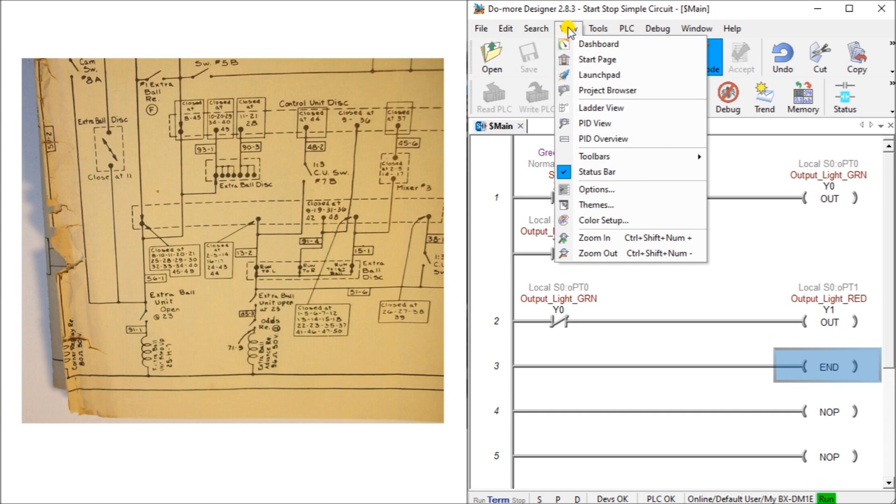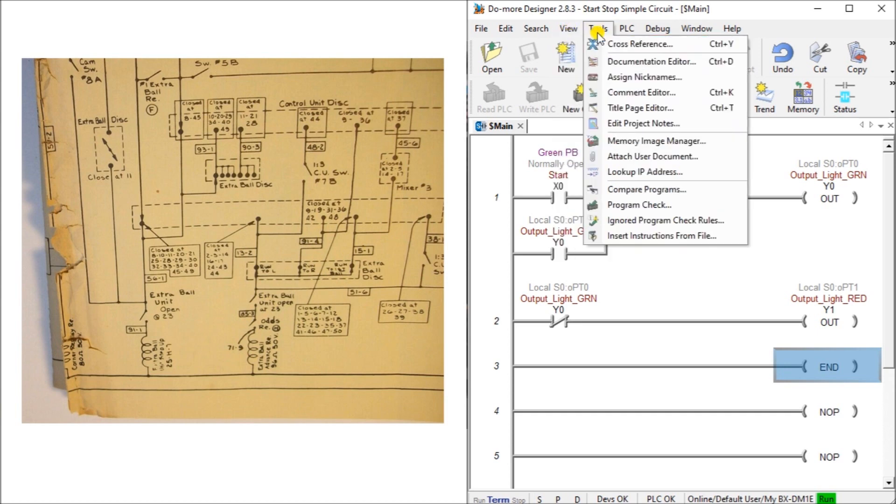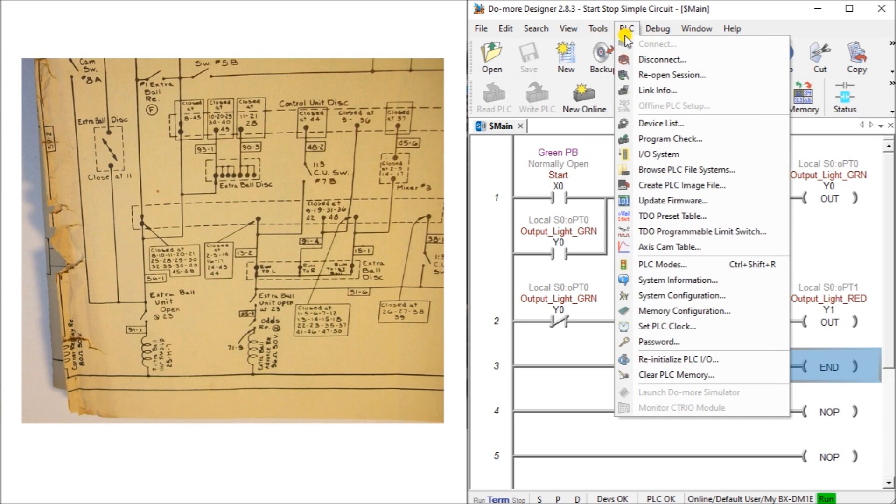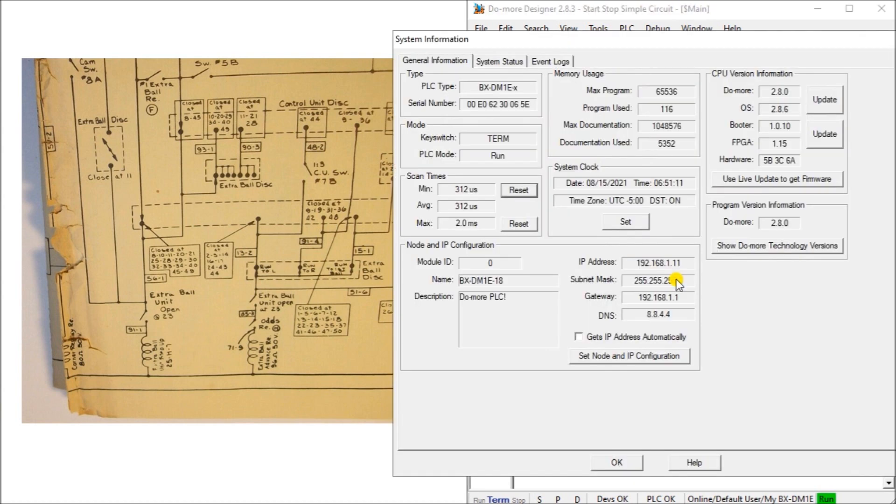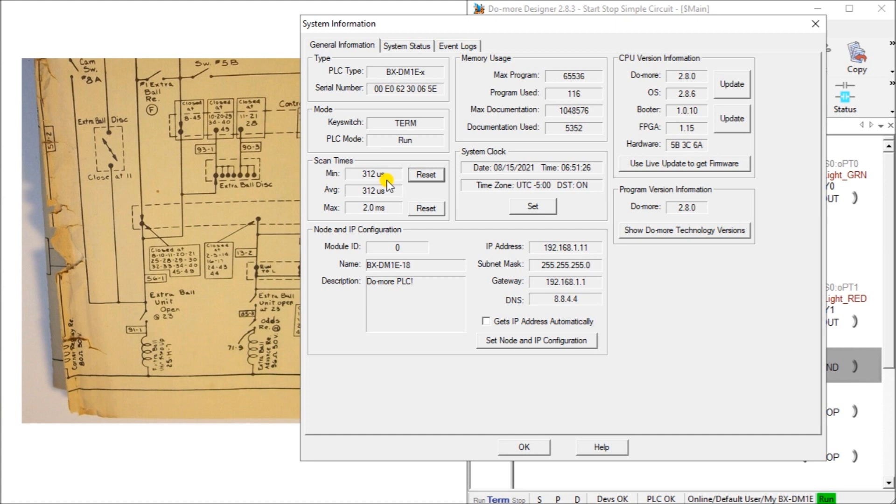We can actually view what's going on here by hitting the view and then we can look at the PLC system information. And under system information, we can actually see here that we have the scan times. Our minimum scan time right now is 312 microseconds. So we're almost going about 3 kilohertz right now. So it's constantly solving that logic. And our maximum scan time was 2 milliseconds.